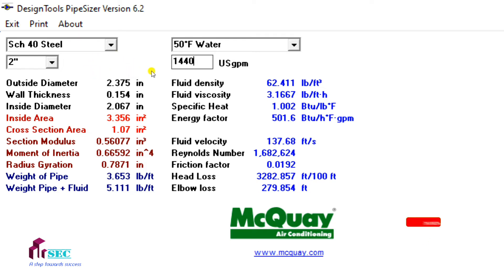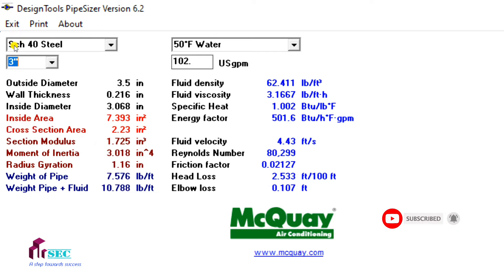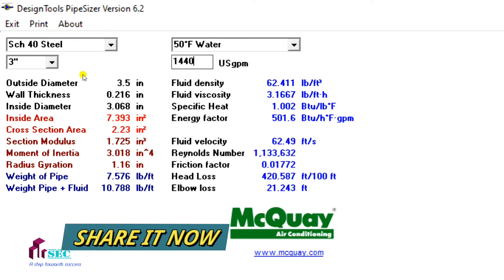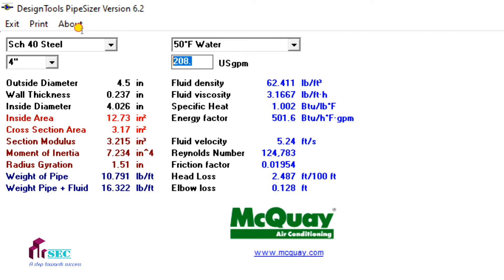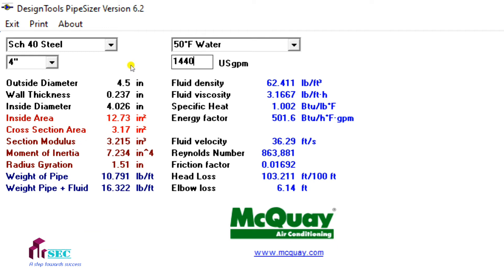It should be less than or equal to 10 feet, so you have to increase the pipe size. I'm going to select 3 inch and enter the GPM again. The fluid velocity is 62 feet per second — again it does not meet the requirement. So I'm going to check with 4 inch and enter the GPM. The fluid velocity is 36 feet per second — again you need to further increase the pipe size.